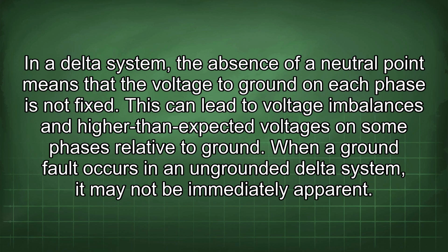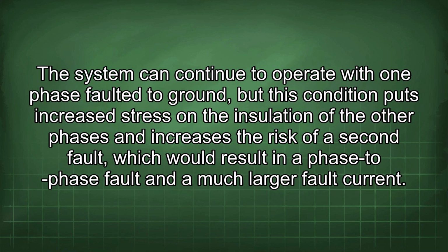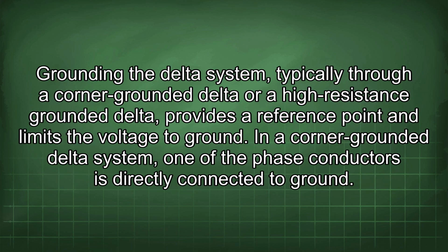When a ground fault occurs in an ungrounded delta system, it may not be immediately apparent. The system can continue to operate with one phase faulted to ground, but this condition puts increased stress on the insulation of the other phases and increases the risk of a second fault, which would result in a phase-to-phase fault and a much larger fault current. Grounding the delta system, typically through a corner grounded delta or a high resistance grounded delta, provides a reference point and limits the voltage to ground.